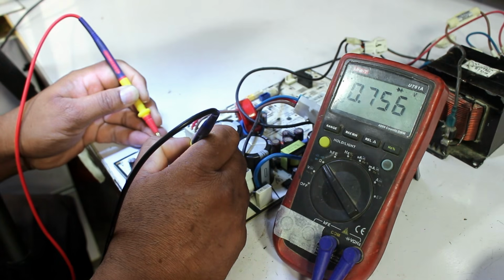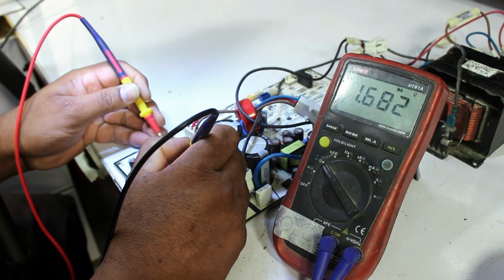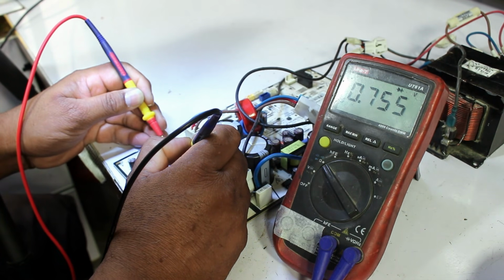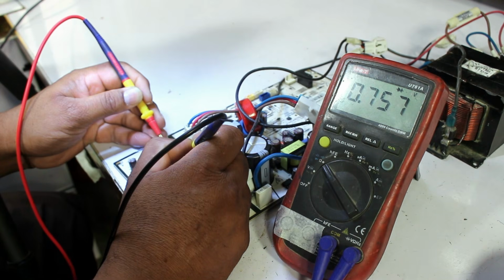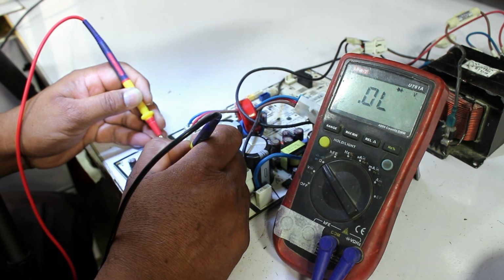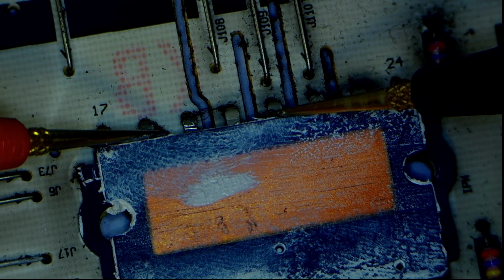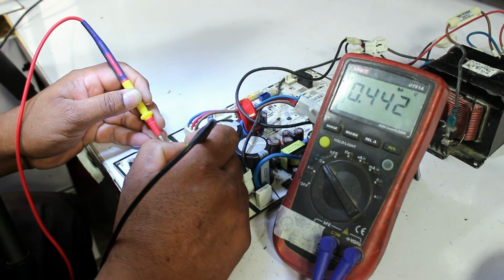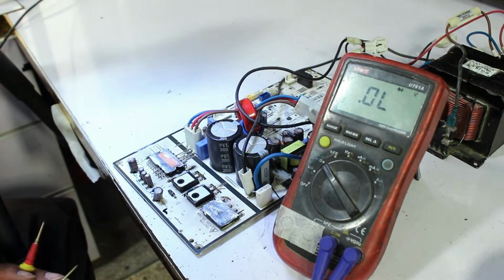Earlier, the voltage drop was not appearing on the negative pin, but now it is. Voltage drops are coming on all 3 pins with the positive points, which means it is fine. Let's also check U, V, and W. The voltage drop should be almost the same, and as you can see, it is the same. So this is also completely fine, there is no problem in it.